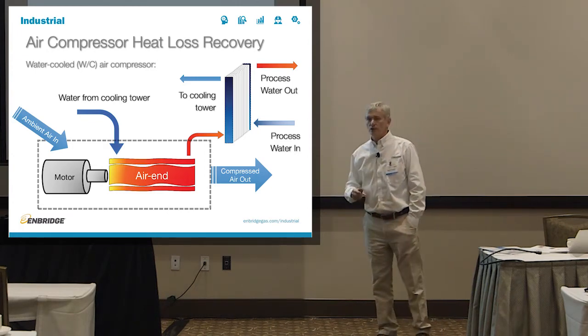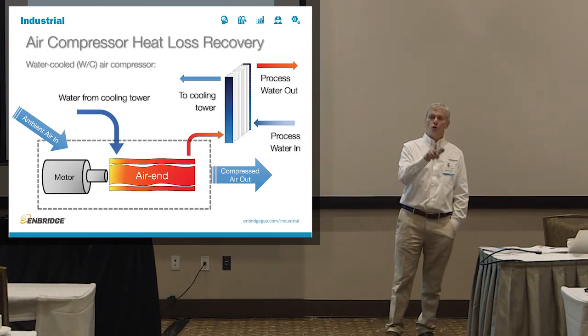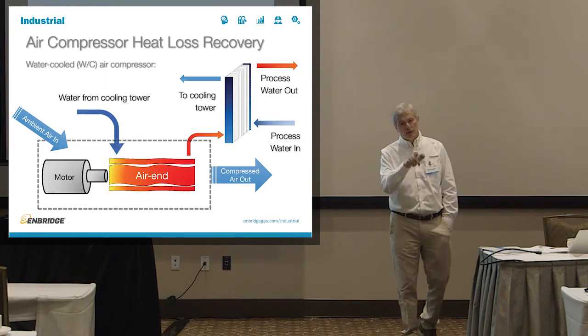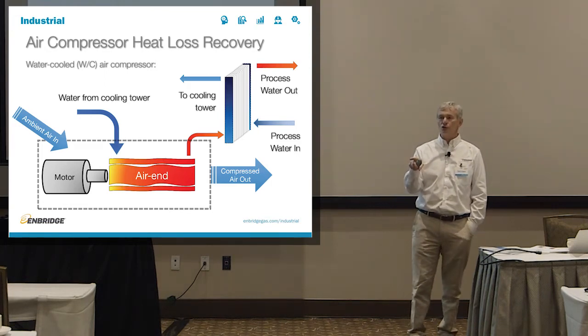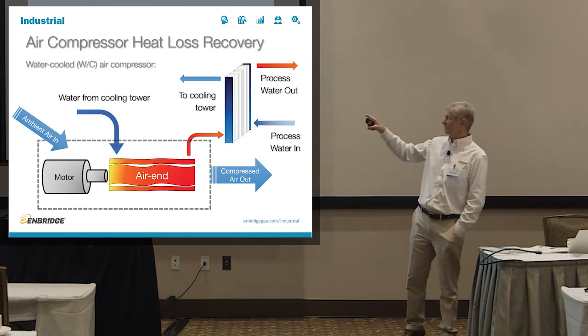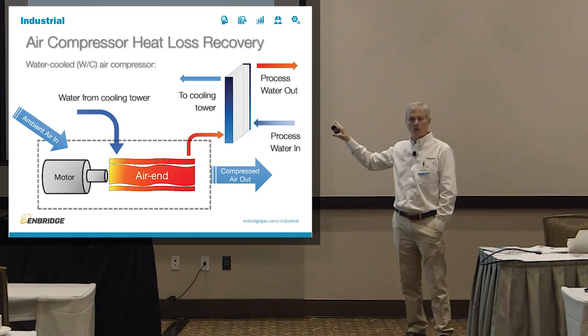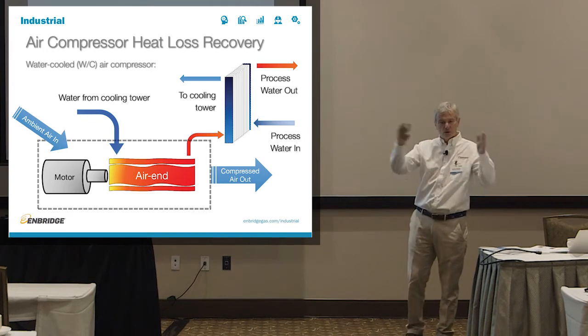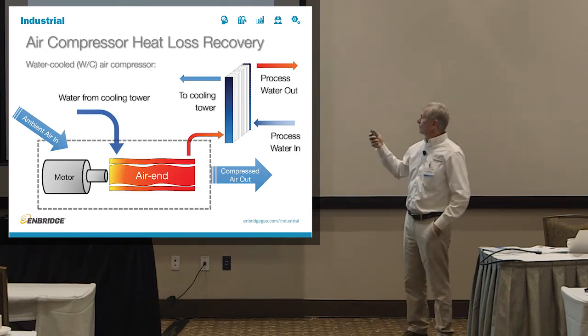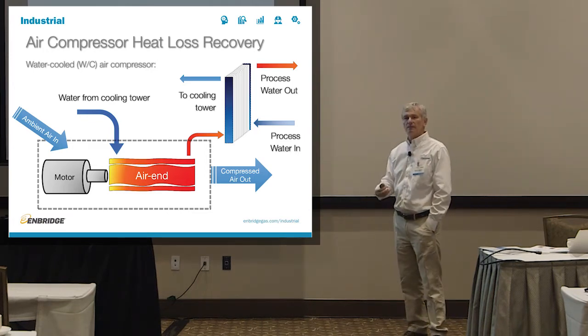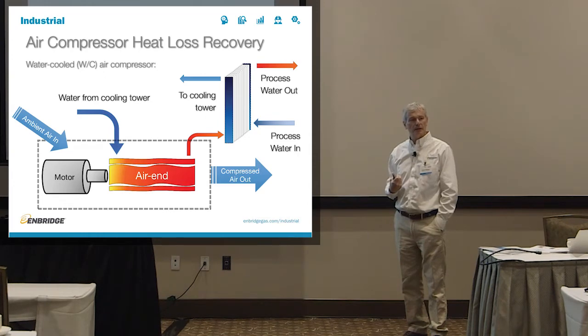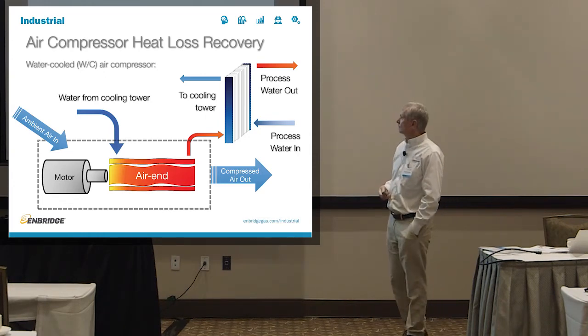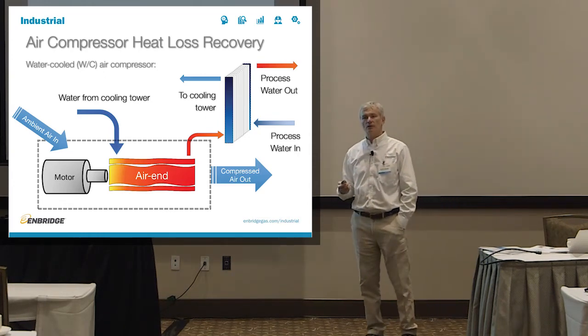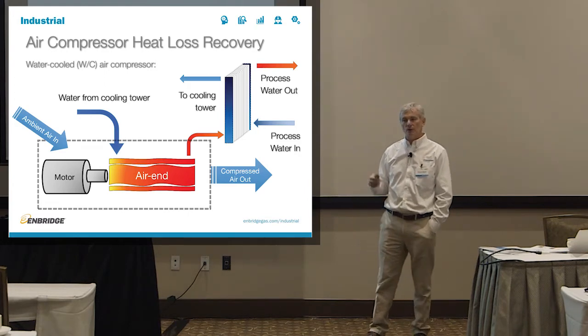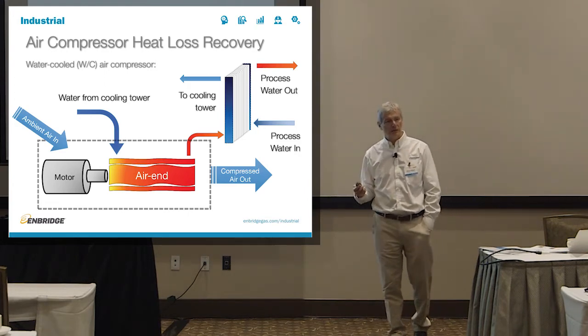On a water-cooled compressor, you usually have a link from the water cooling tower into the compressor heat exchanger, where it then cools the oil that actually cools the compressor. For simplicity, I'm just showing the cooling tower loop going into the compressor box. So water from the cooling tower comes in, takes the heat out of the air end, and now it would be nice to put it into the heat exchanger, because that heat is a valuable heat and there is a lot of it.